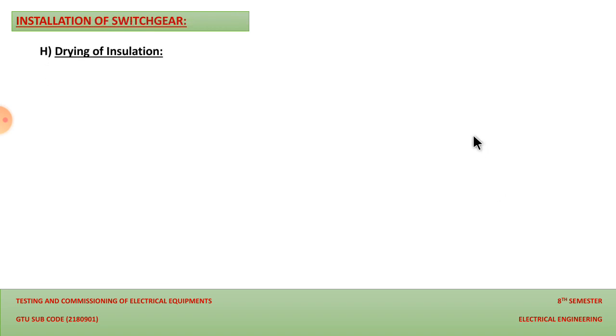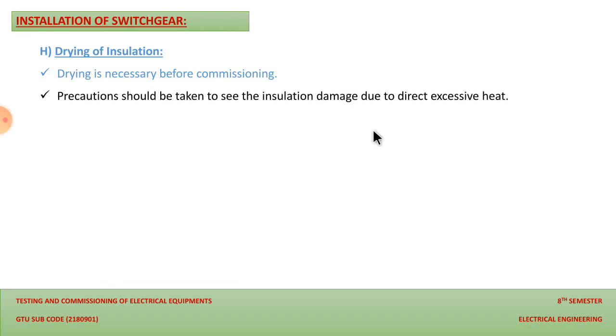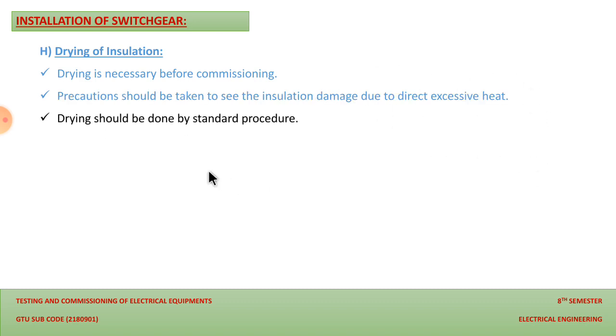Then the next point that we should keep in mind is drying of the insulation. Drying is necessary before commissioning, and precaution should be taken to see that the insulation is not damaged due to direct excessive heat. And the drying should be done by standard procedure, because as we have not used our switch gear for certain days after we received it from the manufacturer, we have to check all the moving mechanism and the level of insulation before we take the switch gear for our operation in the system.